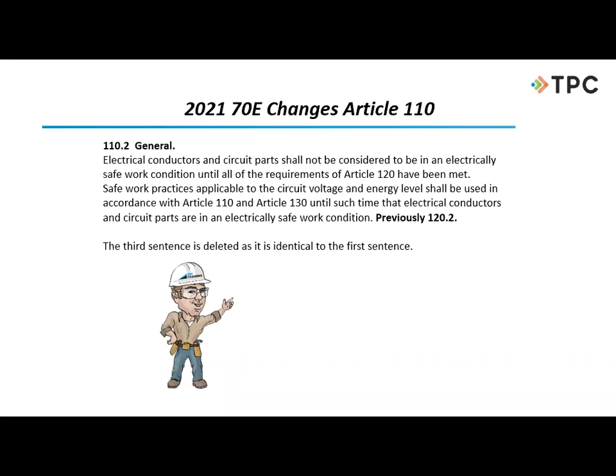110.3 was a bit of a semantic change, telling us about putting equipment into an electrically safe work condition. There are a couple conditions that have to exist: if we go inside the limited approach boundary for anything other than troubleshooting, they really want that to be in an electrically safe work condition. Or if we're going to interact with the equipment in a way that could increase the chances of exposure to an arc flash hazard - for example, racking a breaker in or stabbing onto a bus duct - those things do increase the chances of an arc flash.